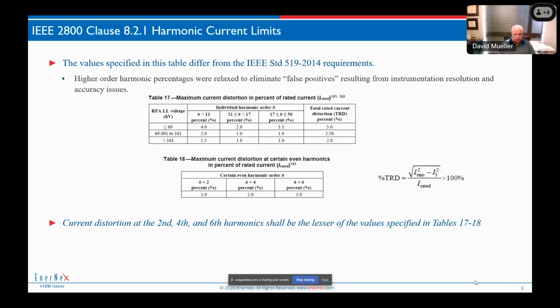First of all, we set harmonic current limits. As I said, we've got limits in a table, and we can actually measure post generation. When we get the plant, we'll typically go out for a couple of weeks. We'll install a monitor. We'll measure. We'll run the statistics, and we don't have to meet the limits all of the time.